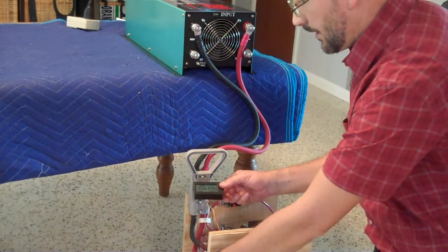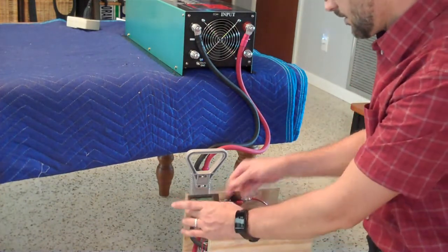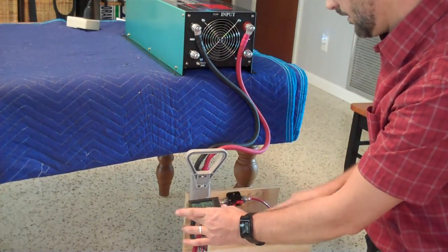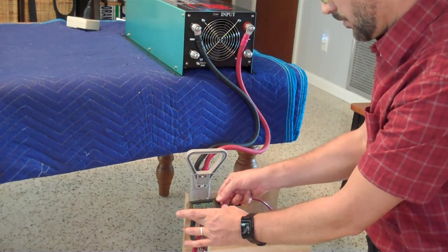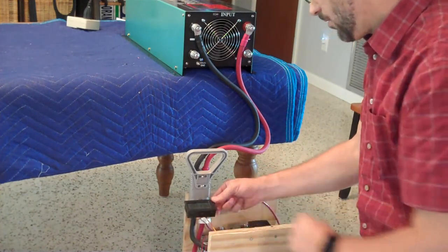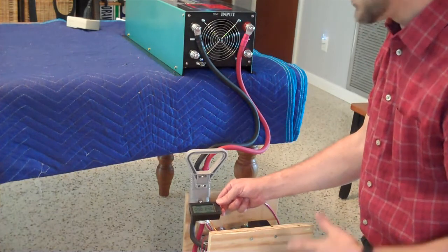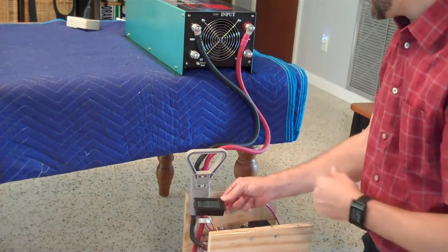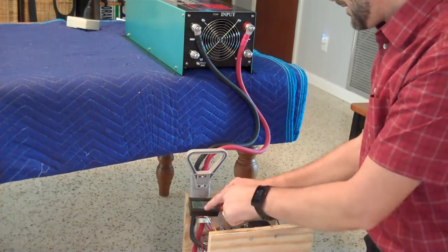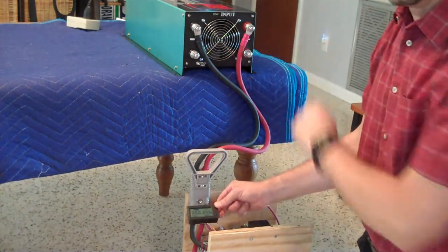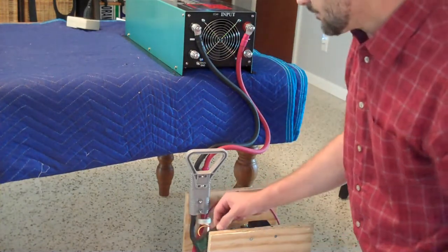So I'm still holding this down, turn it on, now I can release this, and now there's no current flowing through the pre-charge circuit. It's all going through the main 200 amp circuit breaker. And we're at 24.5 volts, 0 amps. It's actually drawing 0.01 amp. We know that because we measured it with a more accurate meter. But, you know, it's not drawing much when the inverter's turned off. So let's turn on the inverter.